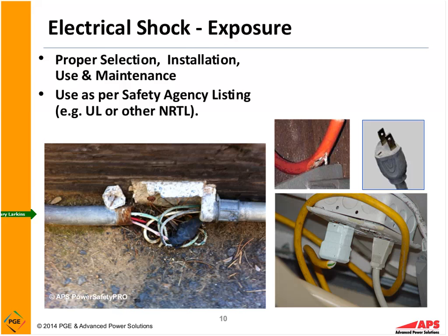And of course, up here we see that the cord is damaged. One of the big shock hazards here, we see that the cord is damaged as well, the connection to the cord cap. And this is another big one where we have a three-prong cord or three-prong device, let's say a drill that uses a three-prong cord, where the third prong, the equipment grounding conductor, is missing. These are also very, very important items that we check on our cords. If that ground pin is missing or not functioning properly, we're definitely presented with a major shock hazard.